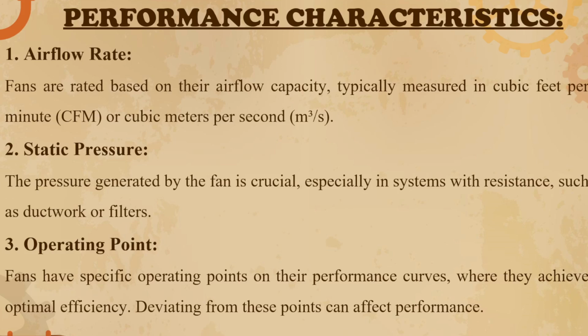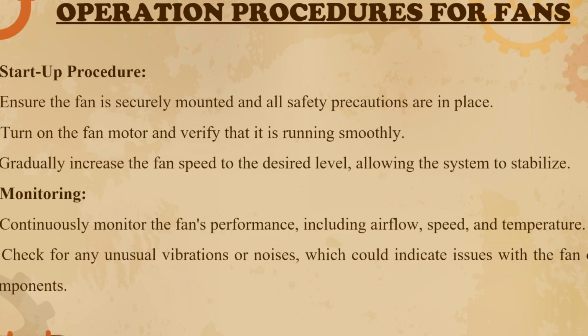Third performance characteristic is the operating point. Fans have specific operating points on their performance curves, where they achieve optimal efficiency. Deviating from these points can affect performance. Proper operation and maintenance of fans are essential to ensure efficient airflow, prevent breakdowns, and ensure the safety of personnel working with or around the equipment.